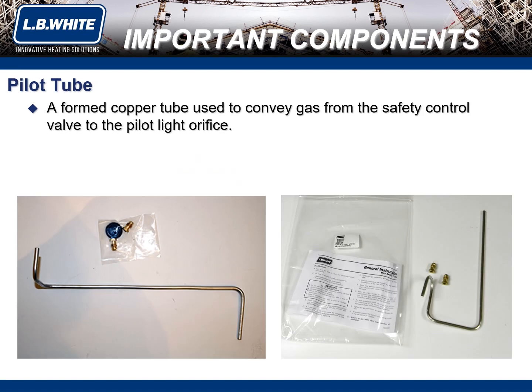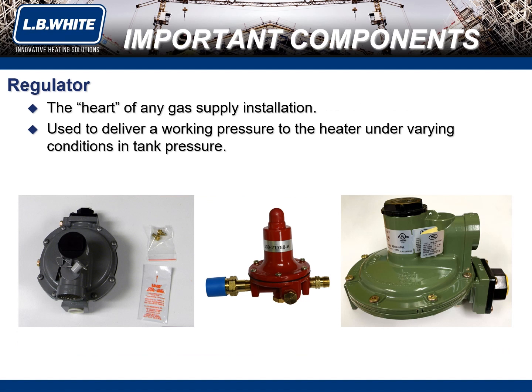A pilot tube is a formed copper tube used to convey gas from the safety control valve to the pilot light orifice. A regulator is the heart of any gas supply installation. They are used to deliver a working pressure to the heater under varying conditions in tank pressure.